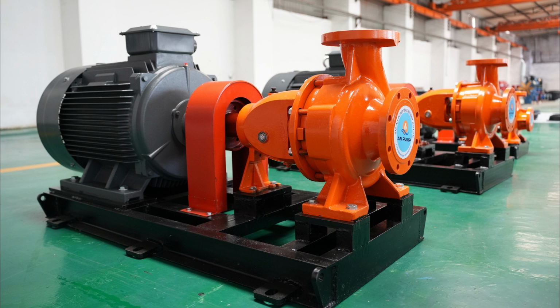Alignment is key. What about the piping? Piping configuration can make or break your performance. You want nice, straight runs of pipe going into the pump inlet. Avoid bends or elbows right near the suction, they can create turbulence and reduce the NPSH we talked about. Make sure your suction and discharge lines are the right size for your flow rate and head, and don't forget to support those pipes properly to prevent stress on the connections.